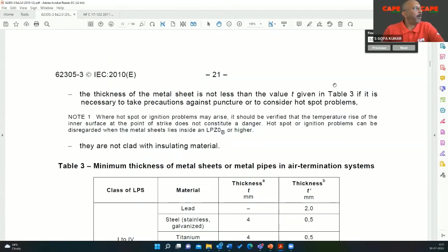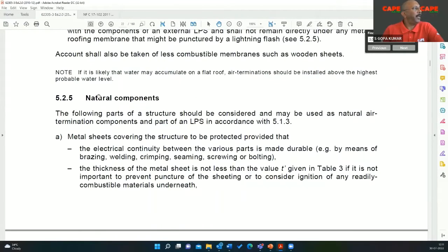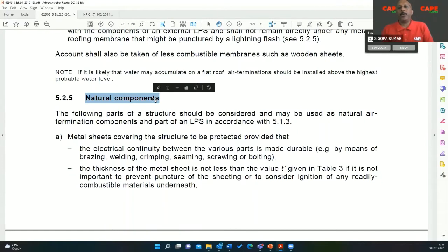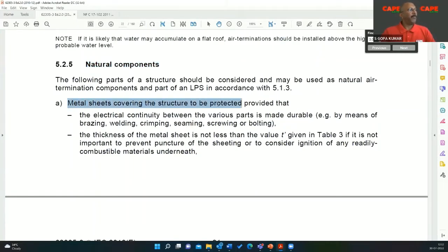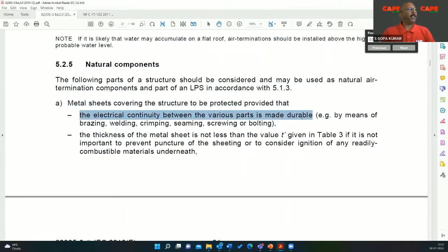It is not on page number 11 exactly, but here is the table. Minimum thickness of metal sheet or metal pipes in air termination system. This part explains the use of natural components. What is a natural component? You have a PEB building with a metal sheet at the top, and that metal sheet is a good conductor — it can be used as an air termination provider. The metal sheet covering the structure must provide electrical continuity between various parts made durable.